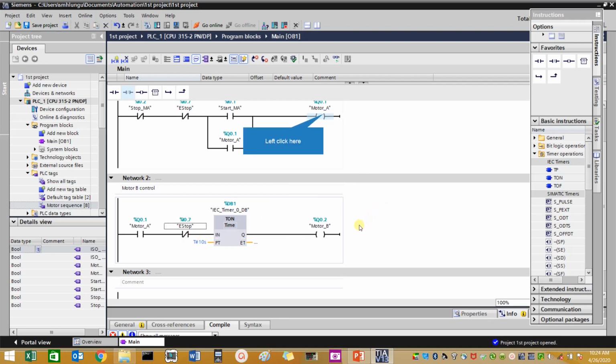This is just for safety, because in any case, this delay on timer can never work without power. Those who are electricians, engineers or technicians know how to wire a delay on timer. If you wire it up, it only counts, it only times, when the coil is energized. As soon as you take away power from it, it stops whatever it's doing.